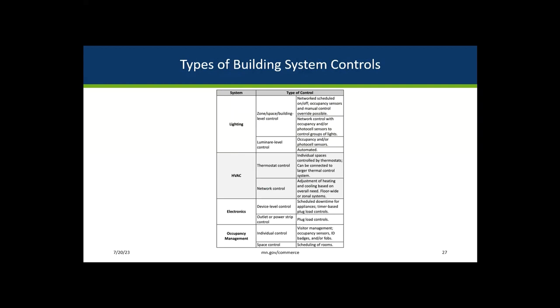The type of controls that are available for the different building systems will help to define the appropriate level of intelligence needed for that space. In this table, the controls are shown for four building systems. The lighting system can have either a zone, space, or building level control, or luminaire level control. The HVAC system can be controlled by thermostats in the space or by networked controls through the building automation system. Plug loads can be controlled on the individual device level or via outlet or power strip control. And finally, occupancy management can be controlled by the individual or by the space.